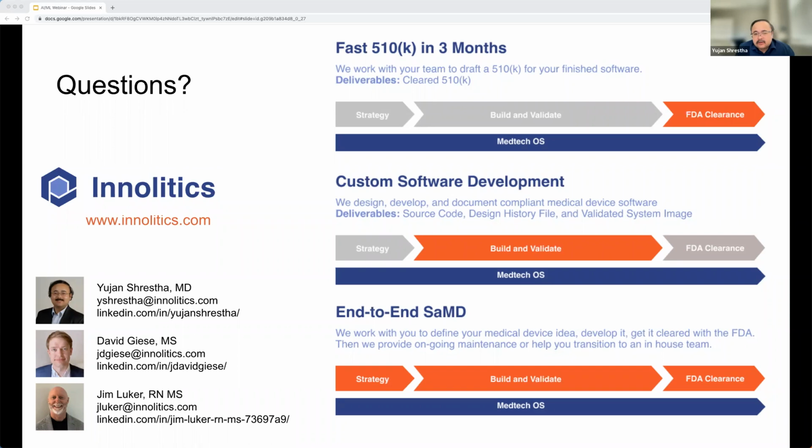Do you have any suggestions for early stage companies regarding process that should be set up from the start? Yes, ideally the most cost effective way is if you do all of this from the start, so we don't have to do retrospective documentation. Be cognizant of knowing when to stop the initial prototyping phase, essentially when you've gained enough confidence that you have something commercially viable and you're going to go forward with it. Then you want to convert that prototyping into something more compliant with FDA. The sooner you do that, the less retroactive documentation you'll need to do. So that would be my suggestion for companies: get the process going as soon as you can.